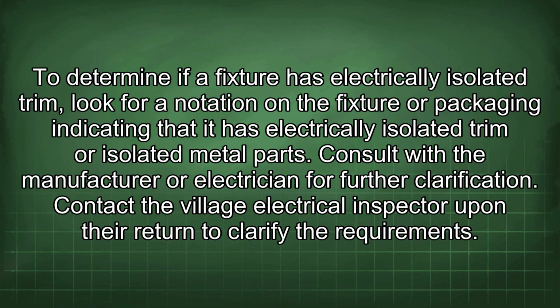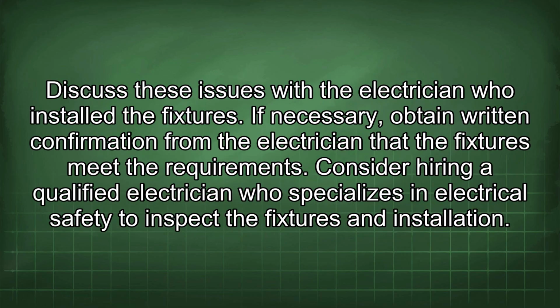To determine if a fixture has electrically isolated trim, look for a notation on the fixture or packaging indicating that it has electrically isolated trim or isolated metal parts. Consult with the manufacturer or electrician for further clarification. Contact the village electrical inspector upon their return to clarify the requirements. Discuss these issues with the electrician who installed the fixtures. If necessary, obtain written confirmation from the electrician that the fixtures meet the requirements. Consider hiring a qualified electrician who specializes in electrical safety to inspect the fixtures and installation.